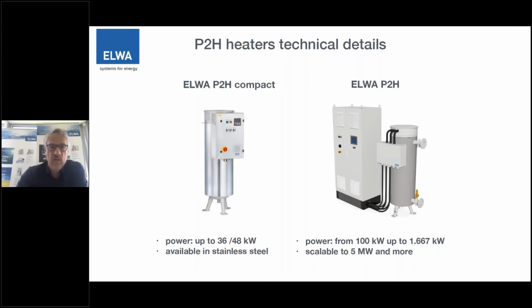Now we've developed a system where we have the control unit and switching cabinet plus the heater on a combined frame, allowing us to deliver complete units without the need for any wiring on site. If you need more power than 1.6 or 1.7 megawatt, we just add units, so we can scale up to large powers, like for a project I'm going to show you now.